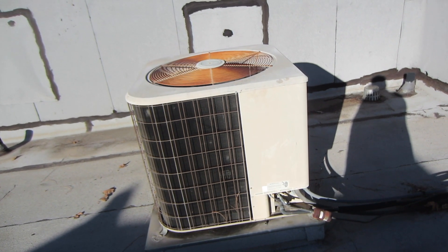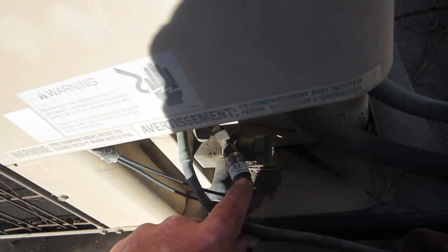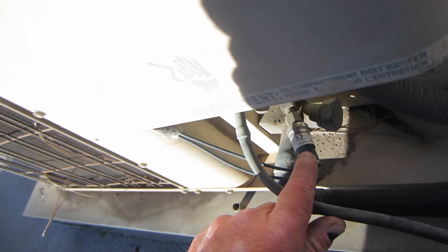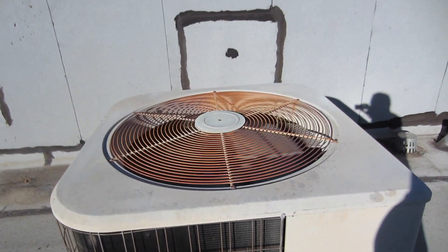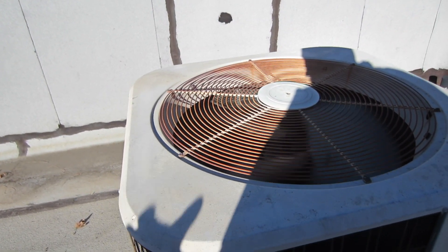So what I did is I just put a head pressure controller on here — 325 and it cuts out at 225. So after the fan motor cuts on it's going to pick up less heat, it's going to lower my head pressure. That way I don't damage the compressor.